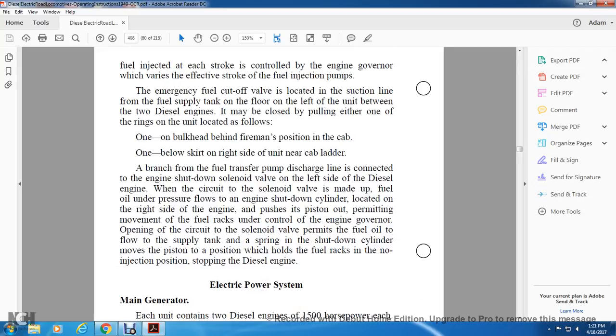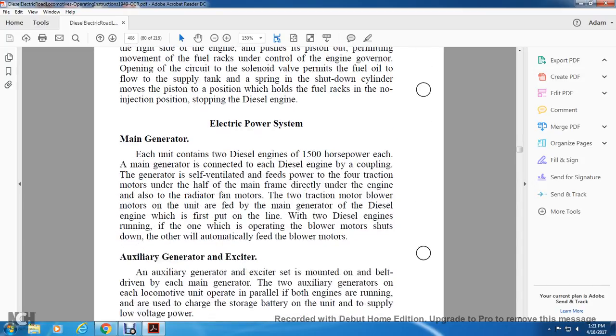The branch from the fuel transfer pump discharge line is connected to the engine shutdown fuel solenoid valve on the left side of the diesel engine. With the circuit of the solenoid valve made up, the fuel oil pressure flows for the engine, and the shutdown cylinder located on the right side of the engine pushes its piston out, permitting the movement of the fuel racks under the control of the engine governor. Opening the circuit for the solenoid valve permits the fuel oil to flow to the supply tank, and the spring in the shutdown cylinder moves the piston into position, which holds the fuel racks in the non-injection position, stopping the diesel engine.